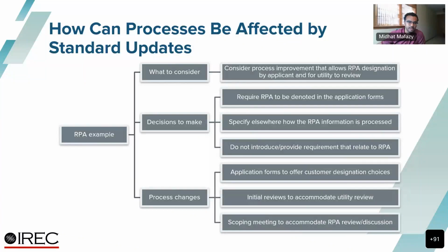Next slide. Here we wanted to share an example of how the updated 1547 standard can affect the interconnection process. We mentioned RPA earlier—reference point of applicability—which is the location where the interconnection and interoperability performance requirements specified in the base standard are met. Such a location can affect evaluation and commissioning requirements. Per 1547-2018, the RPA location can be at the point of common coupling (PCC), at the point of connection (POC), a point in between, or there could be multiple RPAs for different DER units.